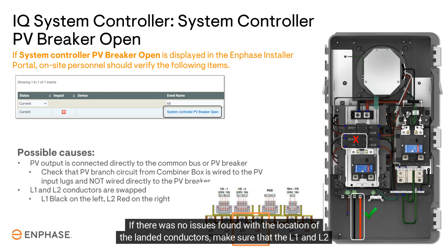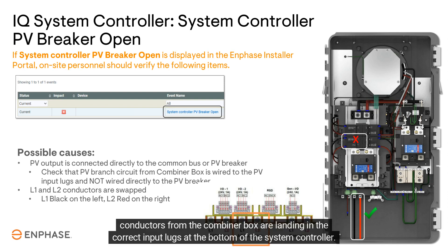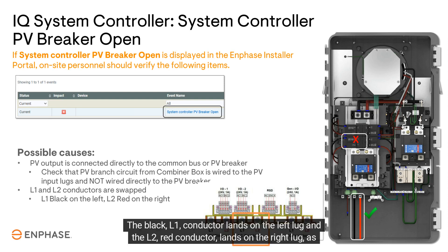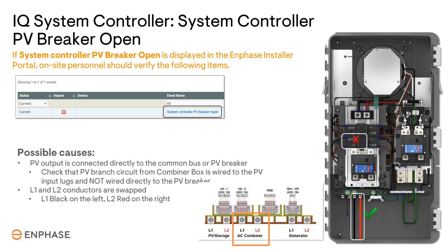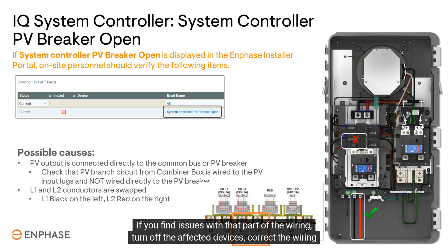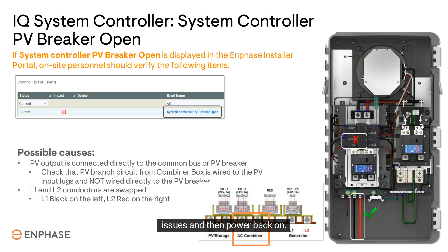If there were no issues found with the location of the landed conductors, make sure that the L1 and L2 conductors from the combiner box are landing in the correct input lugs at the bottom of the system controller. The black L1 conductor lands on the left lug and the L2 red conductor lands on the right lug, as shown in the images. If you find issues with that part of the wiring, turn off the affected devices, correct the wiring issues, and then power back on.